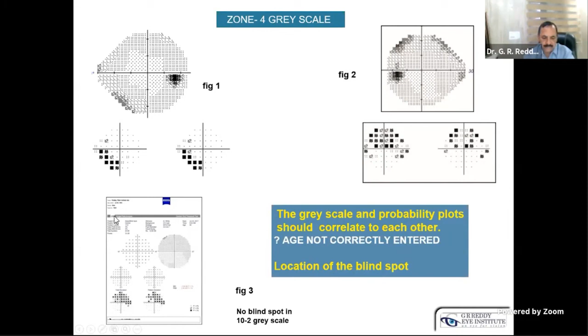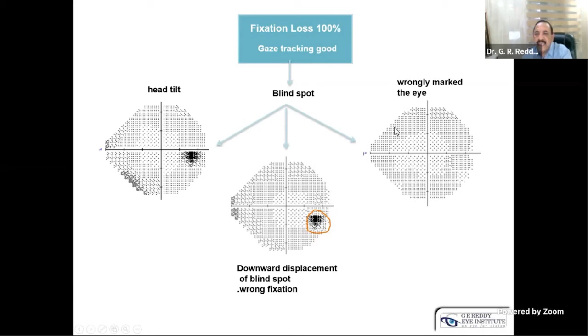If you take, for example, the most important thing is if the fixation losses are 100% and gaze tracking is excellent, that means something is going wrong. There may be head tilt during the test, and the fixation losses will be 100%, and the gaze tracking will be good. And sometimes the blind spot may be displaced downwards. When the patient, after finishing the foveal sensitivity testing, won't shift his fixation to central fixation, he remains fixing at a small diamond, and the blind spot will be located downwards.